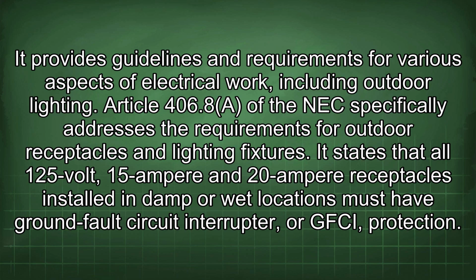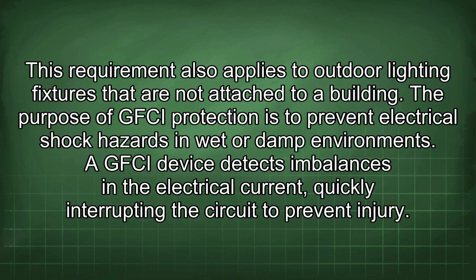It states that all 125-volt, 15-ampere and 20-ampere receptacles installed in damp or wet locations must have ground fault circuit interrupter, or GFCI, protection. This requirement also applies to outdoor lighting fixtures that are not attached to a building. The purpose of GFCI protection is to prevent electrical shock hazards in wet or damp environments. A GFCI device detects imbalances in the electrical current, quickly interrupting the circuit to prevent injury.